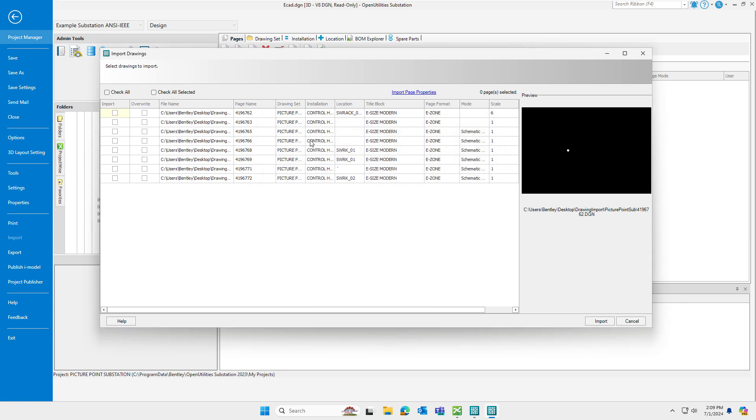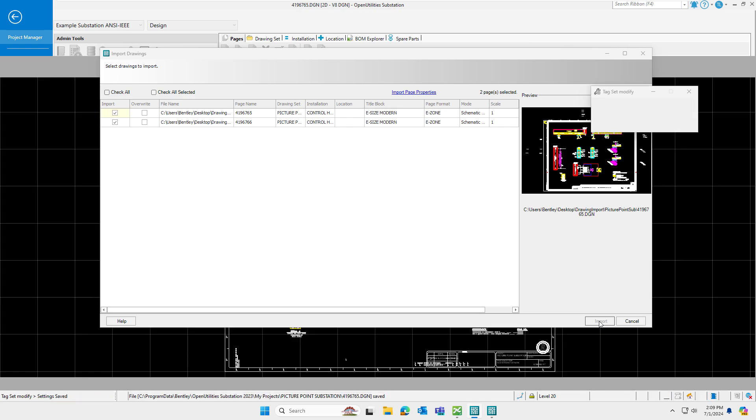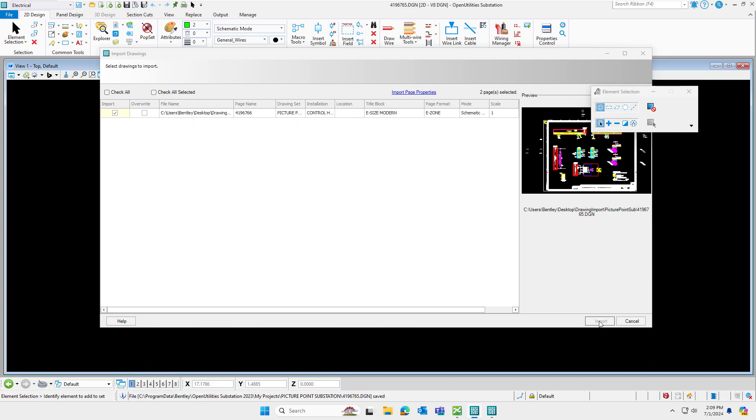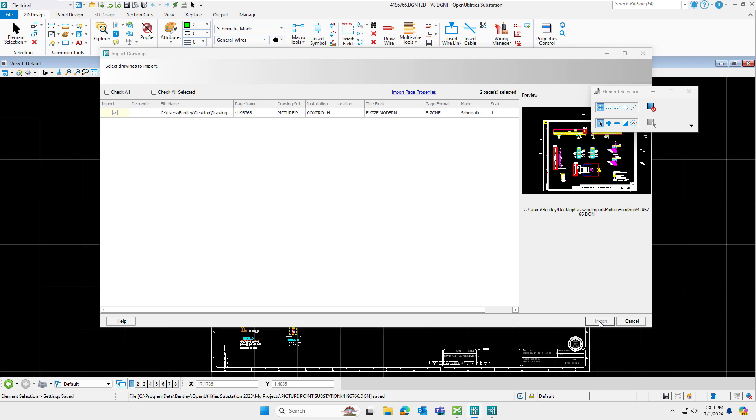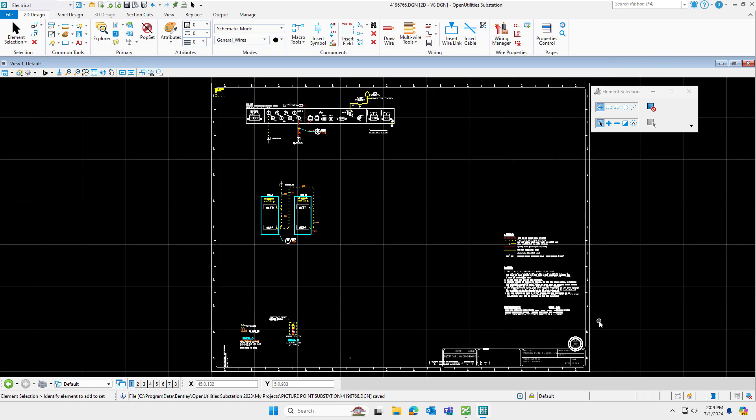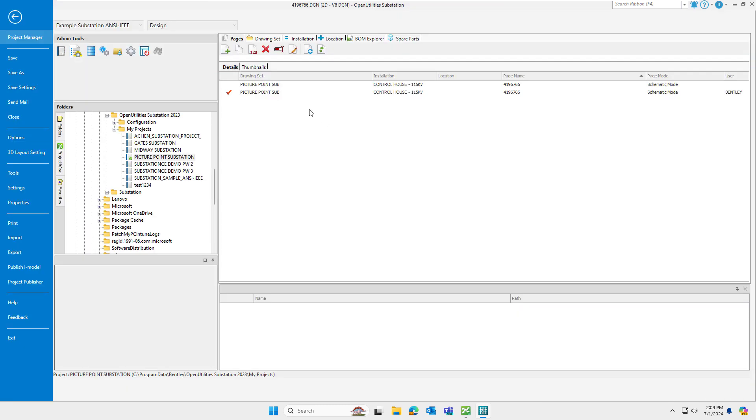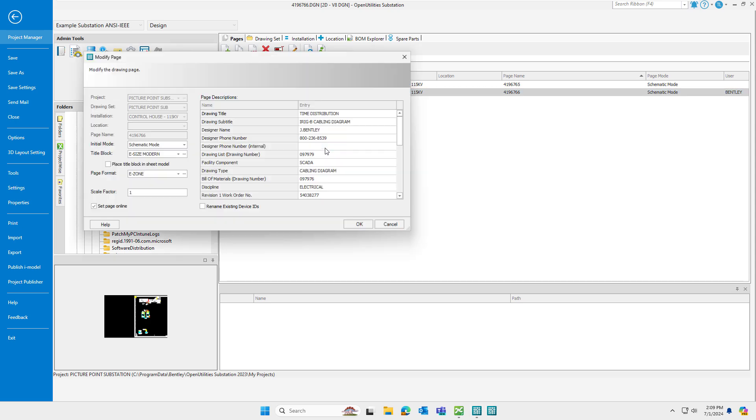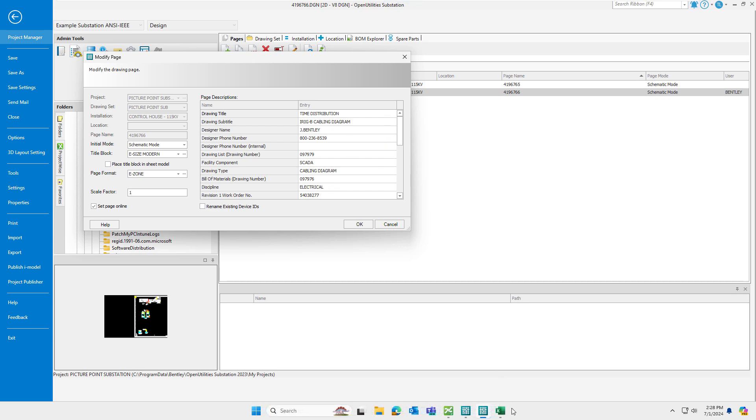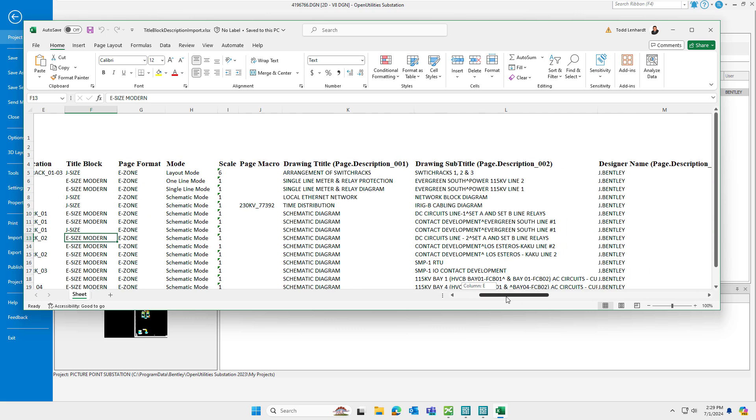Now I can choose some of the files that I wish to import. So I'm just going to choose a couple of these schematic drawings here and I'll complete the import process. During the import process, it's reading that title block information from the Excel file and then importing those values into your Open Utilities substation page descriptions or title block attributes. So for example, the import is complete. I can go ahead and go into the Modify page and you can see this is all the data that came in from that Excel file. Taking a look at the Excel file where the data originated from, here you can see that column A has the file name, column B has the page name, and then you can see the remaining columns for your title block attribute information.